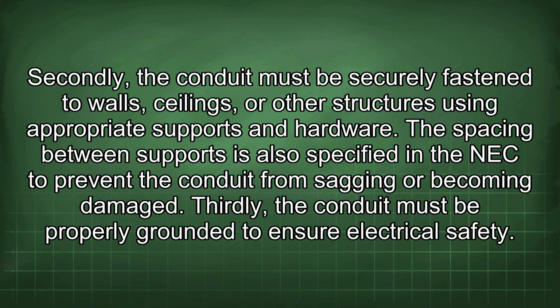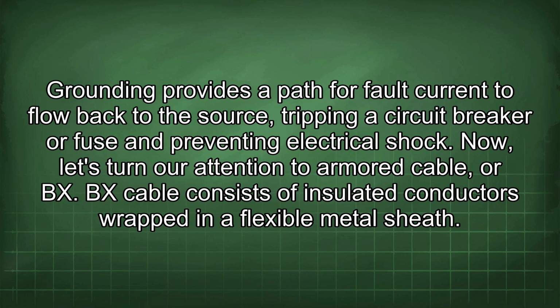Secondly, the conduit must be securely fastened to walls, ceilings, or other structures using appropriate supports and hardware. The spacing between supports is also specified in the NEC to prevent the conduit from sagging or becoming damaged. Thirdly, the conduit must be properly grounded to ensure electrical safety.